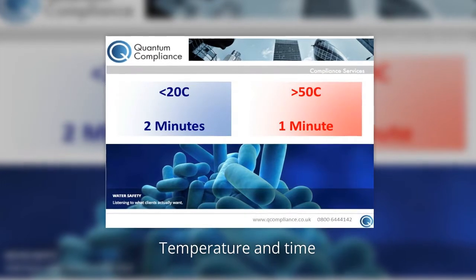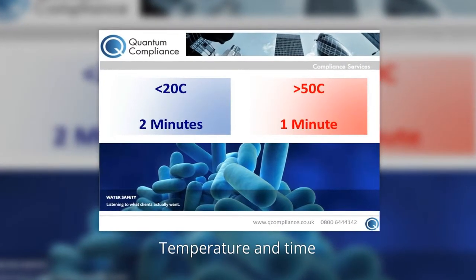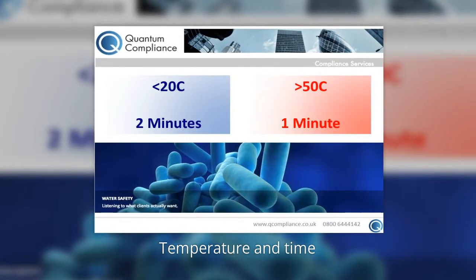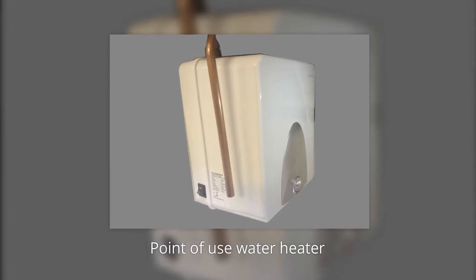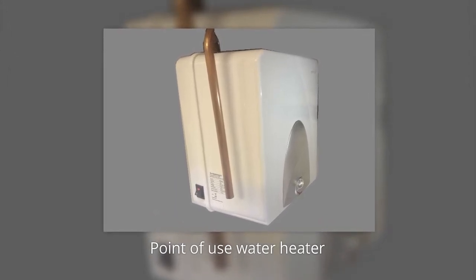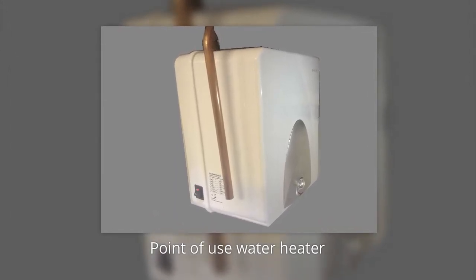So as a reminder: for cold water temperatures, you will need to record the temperature for two minutes, which should not exceed 20 degrees centigrade. And for hot water temperatures, you will need to record the temperature for one minute, which should exceed 50 degrees centigrade. You will also need to be aware of point-of-use water heaters, where the supply of hot water may run out before the end of the one-minute monitoring period.